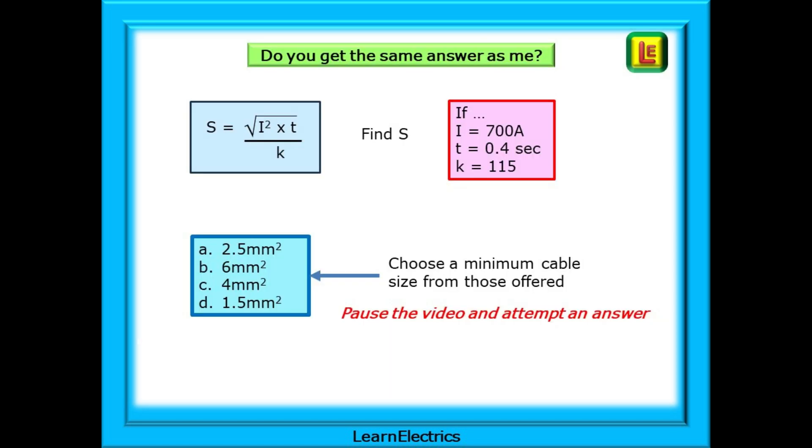It's important that you are able to use this formula correctly so let's have a little calculation to do. This is the sort of thing to expect in an exam or assessment. Using the adiabatic equation shown find S the minimum size earth conductor to satisfy the requirements for the data given in the red box. Then just as in an exam choose the minimum cable size from those offered A B C or D. Pause the video whilst you attempt an answer. The solution is on the next slide.